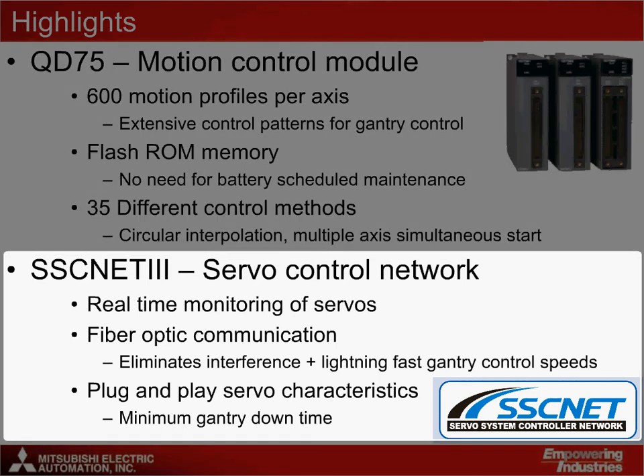The QD75 also uses SSCnet for real-time monitoring of the servo's operation. SSCnet realises high performance and high accuracy devices that could not be attained with conventional pulse train command or analogue commands. The high speed network allows monitoring of the servos in real time, and its fibre optic communication eliminates interference that causes drift in other positioning solutions. Its plug-and-play flash memory also allows quick connection of servos and download of parameters to minimise gantry downtime after maintenance checks.